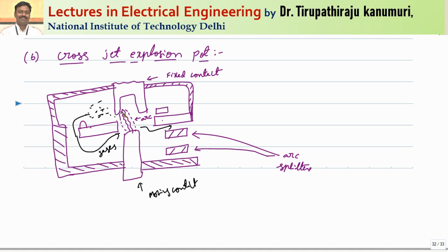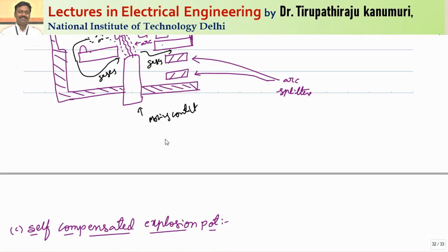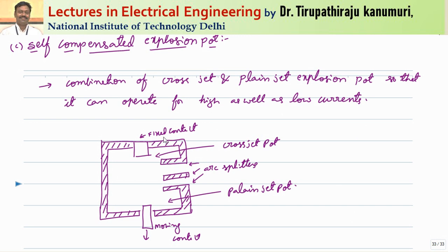The cross jet explosion pot has a disadvantage: it cannot be used effectively for small currents. Whenever there are small currents, whatever gases are produced escape from the arc splitters, sufficient pressure is not created, and the arc takes more length and more time to extinguish. Therefore this design is particularly suited for high fault currents only.